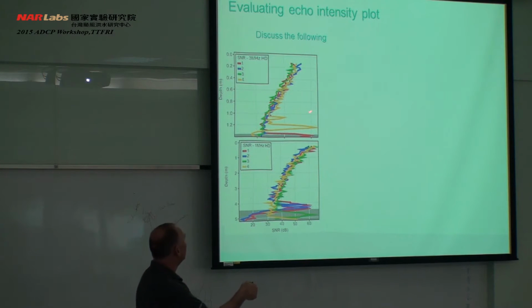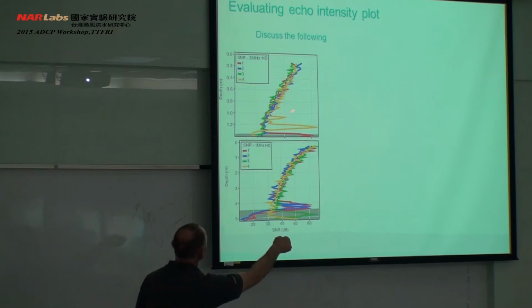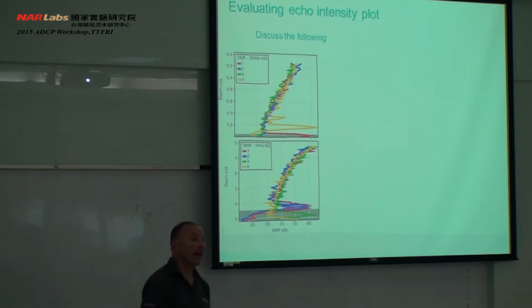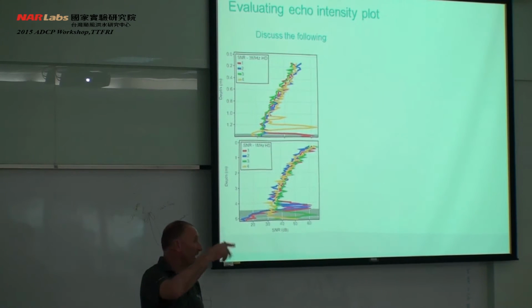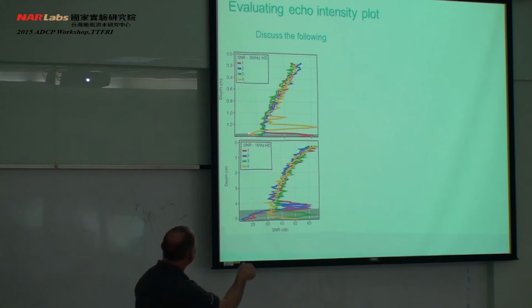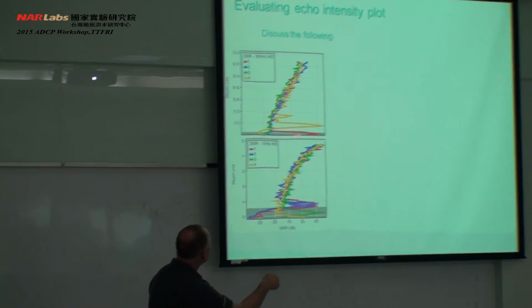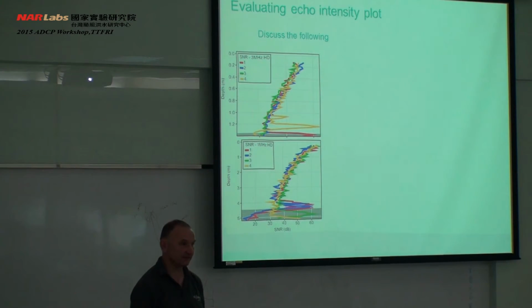The instrument will only use data where we have got 4 good beams of data. So when we use this data down to this point here, down to about 1 metre, it will still store the data beyond, but it will not use it in the discharge calculation. Anything below this point will be extrapolated. This grey line here is where it is determining the mean bed position from the 4 beams.